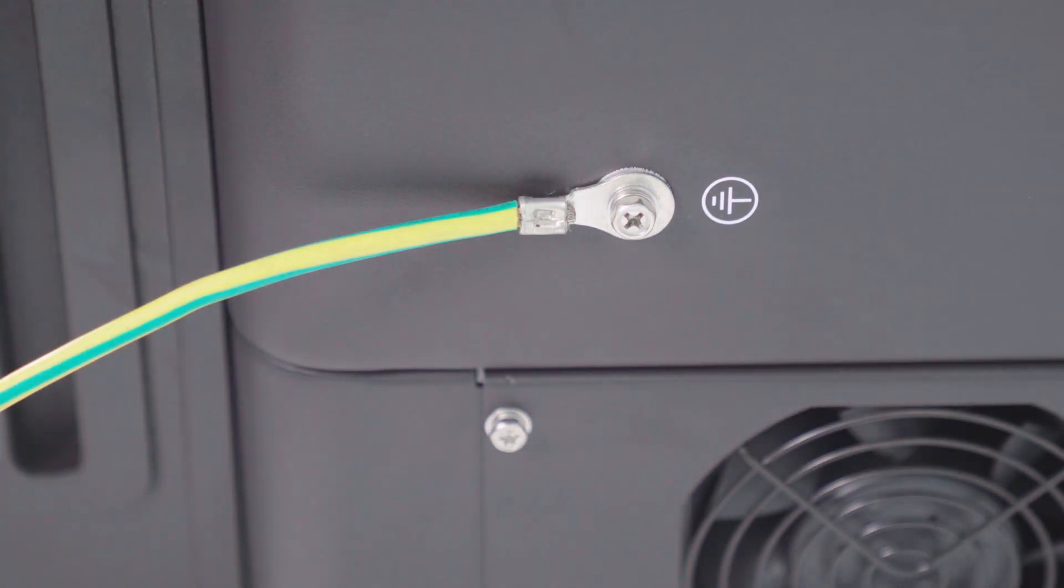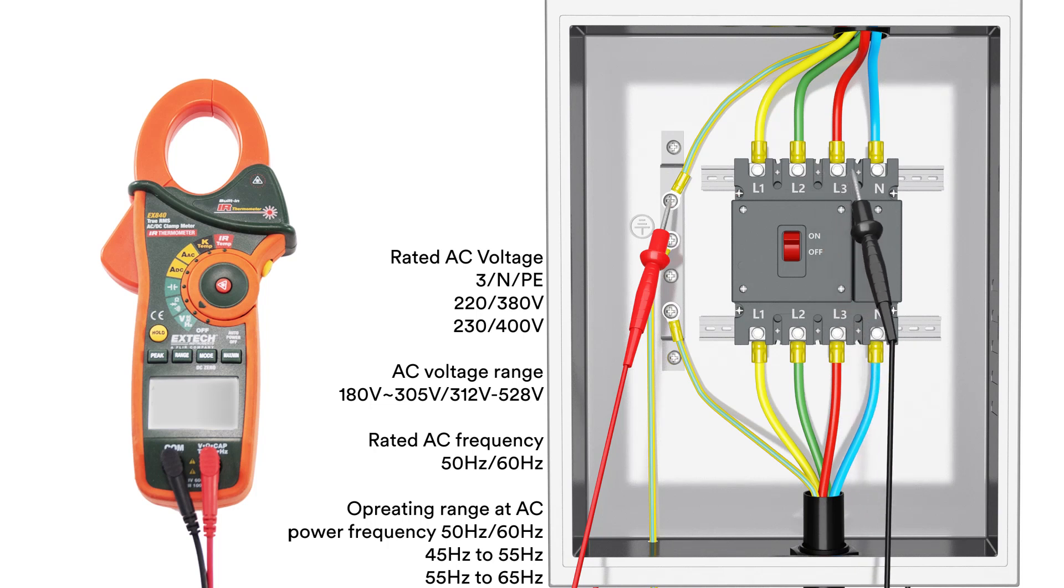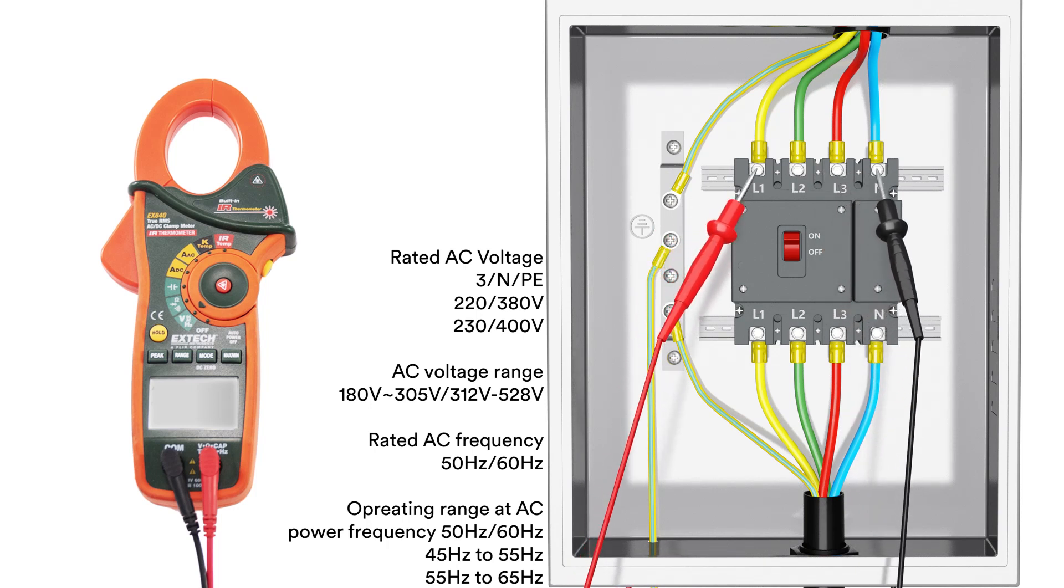Make sure that the inverter's exposed metal surface has a ground connection. Check the PE connection with a multimeter. Check the grid voltage. Check that the grid voltage at the point of connection of the inverter complies with the permitted value.